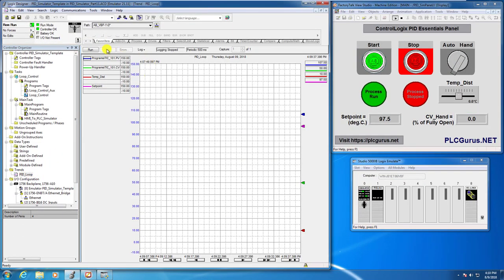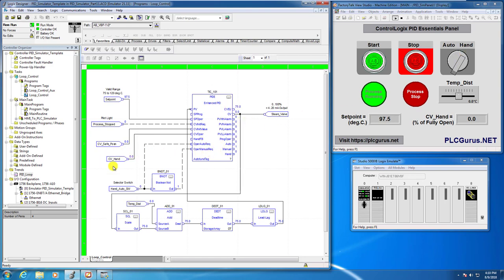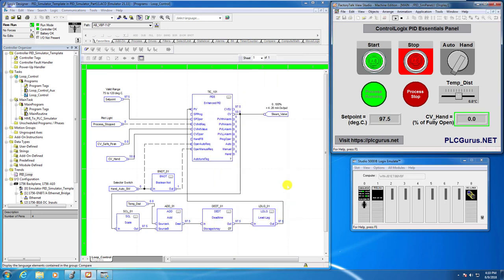Let's head over to our trend and fire that up. We're in hand mode, starting up in open loop control mode. Remember, in hand mode, whatever value we place in CV hand gets output directly to our steam valve — we're allowing the operator to take direct control over the valve position. I'm going to put in our usual 50%, and we know that opening this valve to 50% will get us to the set point of 97.5 degrees, which will provide us with bumpless transfer.